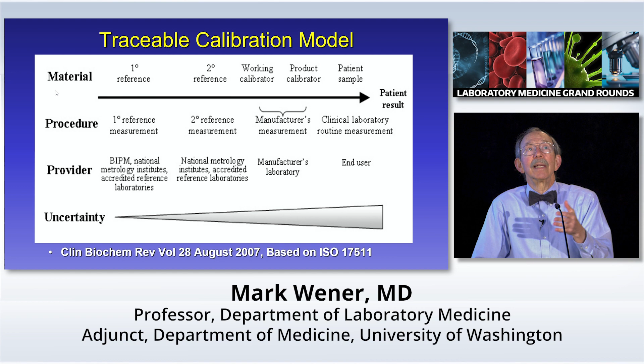So what would a clinical chemist do? And the answer is you make a good standard and find a standard method and a standard approach to determine truth. And there are algorithms for how to do that, starting from primary reference material to secondary reference material, having primary procedures that are essentially the reference method coming from national laboratories, and then working down to secondary and tertiary calibrators, and then the product calibrator that goes into a kit, into a routine lab. And the uncertainty from truth increases, but there's a way to trace it all the way from a primary reference.